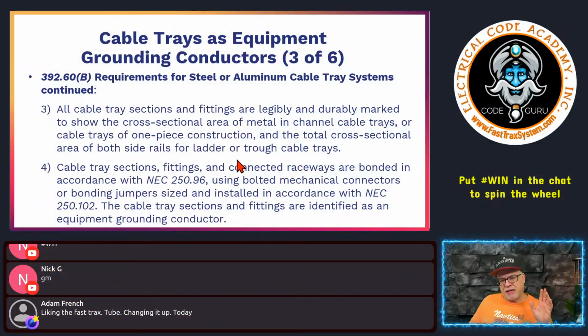Hopefully all these are designed out by an engineer, especially if they're getting to the point where the tray is going to be used as an equipment grounding conductor. Hopefully somebody's done their due diligence. I can tell you as a plans examiner and supervisor of plans examiners, there were plenty of applications where drawings submitted to me had been designed by engineers without putting equipment grounds in a cable tray system, only to find out that what was installed was not a cable tray that could be used as an equipment ground.